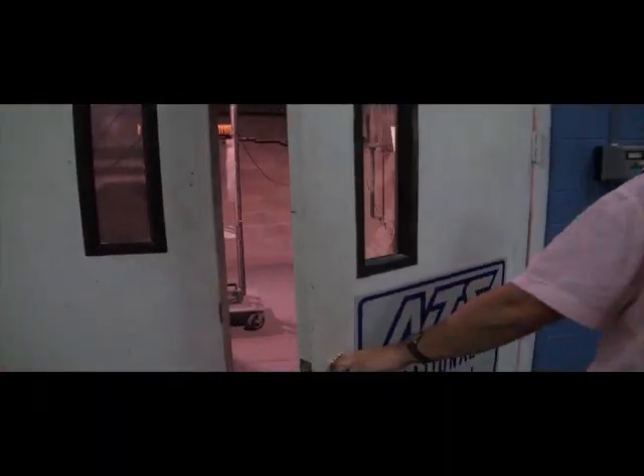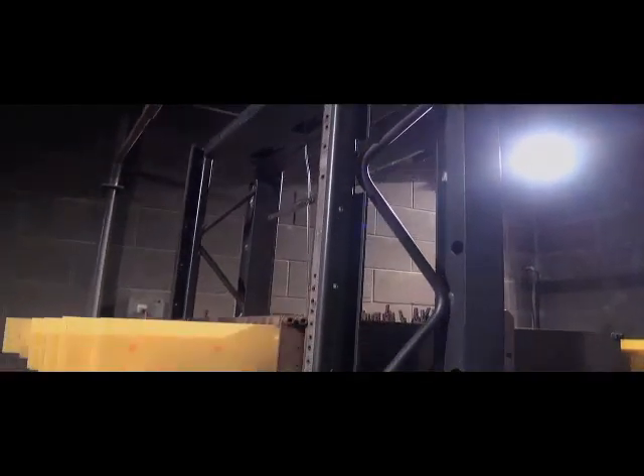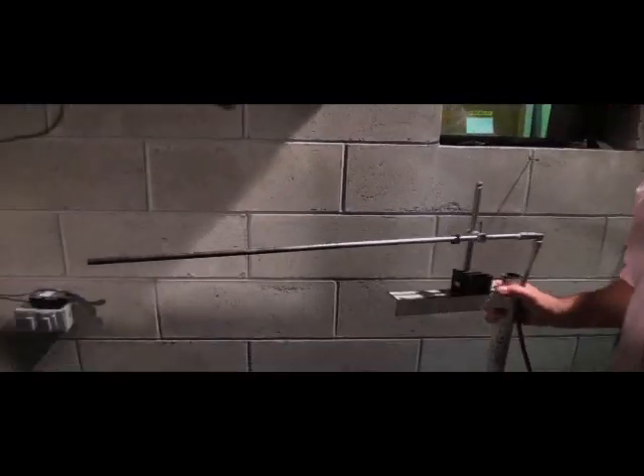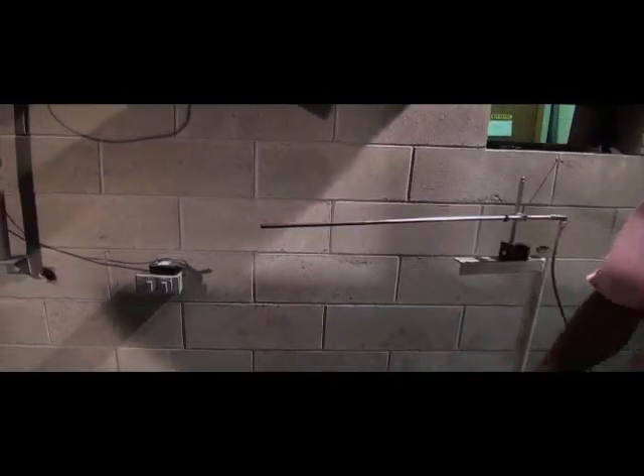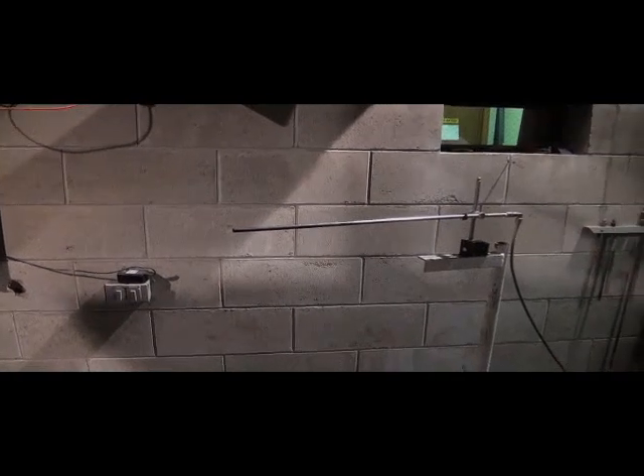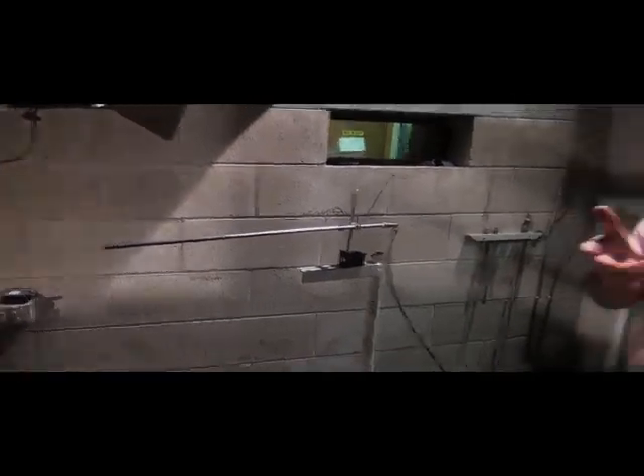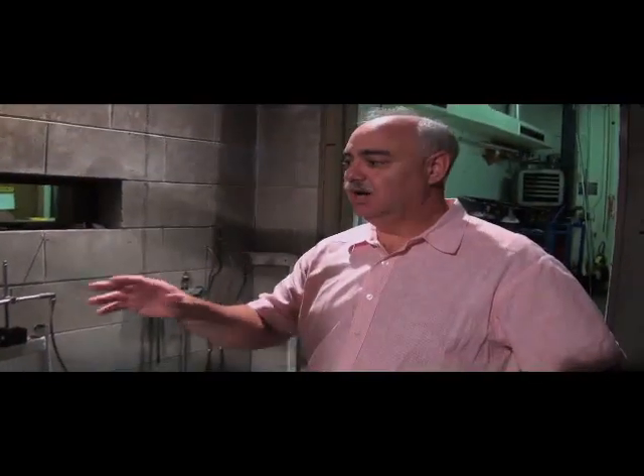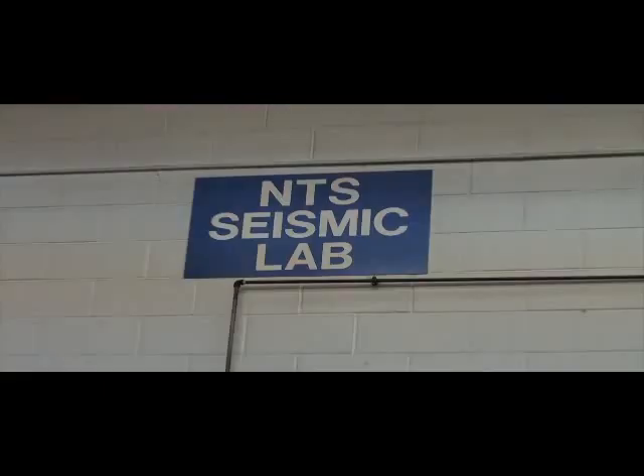This is our telecom flame chamber. So testing here is to GR-63-CORE, NEBS testing. This torch is actually inserted into the component. It's left to burn, and after a period of time, the flame is extinguished, and then we watch to make sure that the equipment will self-extinguish within 15 minutes.